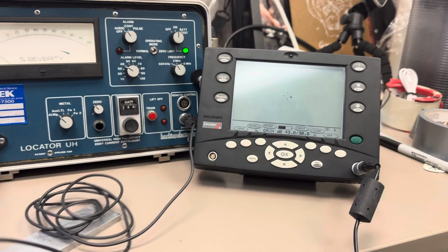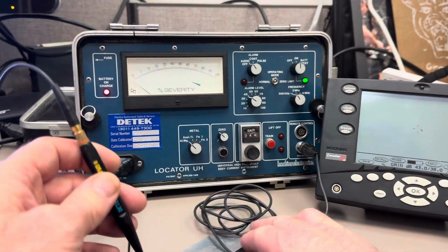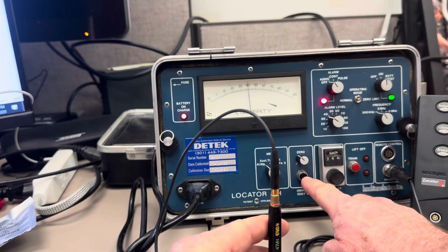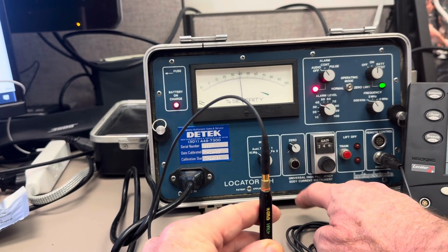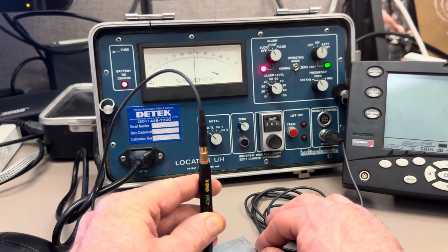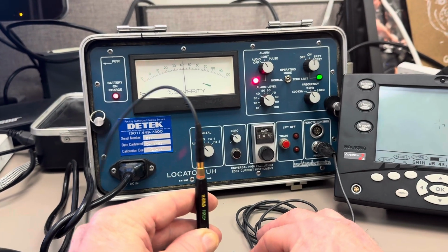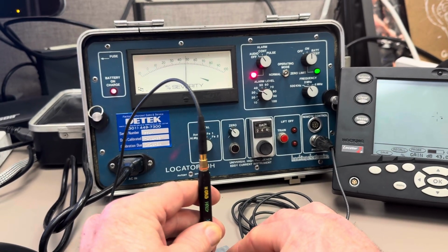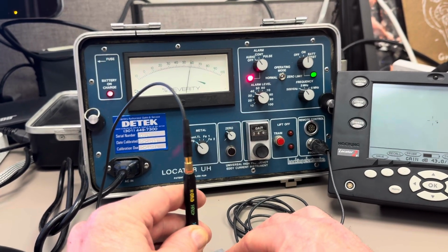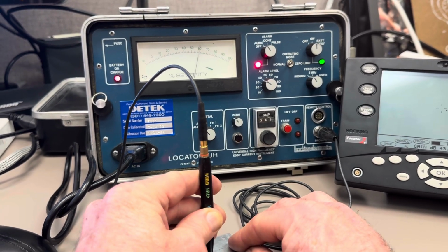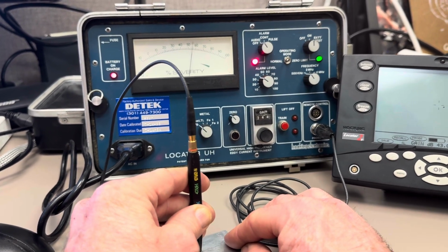Well, first, let's go over to the locator. We're going to take this probe and put it in the material. I don't even know how to calibrate this instrument, but for this particular demonstration, I'll just show you that right now I'm balanced in the middle of the meter. And when I scan over a crack, you get a deflection on the needle right there, see? But if I wasn't looking at this cal block and knew that there was a crack in there, I wouldn't know exactly what's causing that needle deflection.